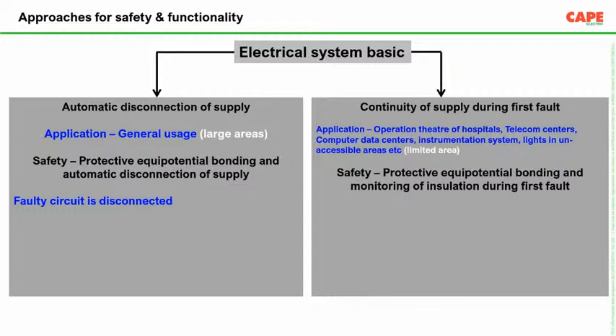And even in case of a dead fault, the first fault, one of the current carrying conductors is connected to the earth. Earth means the metallic object of that area. Nothing happens. So there is no shock, there is no hazard. But during a double fault, the second fault, of course, the system should disconnect. Continuity of supply is for the first fault. Disconnection must happen in the second fault. For that particular disconnection, we have to use devices such as MCBs, RCDs, and so on.